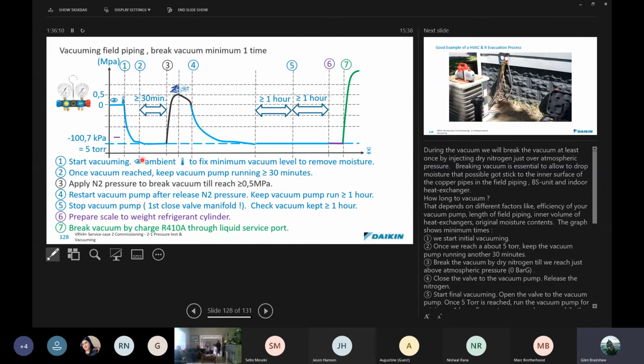We also do a triple evacuation where you can come down in steps and you break the vacuum with nitrogen. You do not need to break it to 35 bar. We're just using nitrogen basically to pick up a bit of the moisture, but a much better way of clearing moisture out of a system is using a nitrogen purge, where you blow nitrogen through the system at a low pressure, around 20 kPa, for anywhere up to 30 minutes, just to try and move out any moisture that's in vapor form.